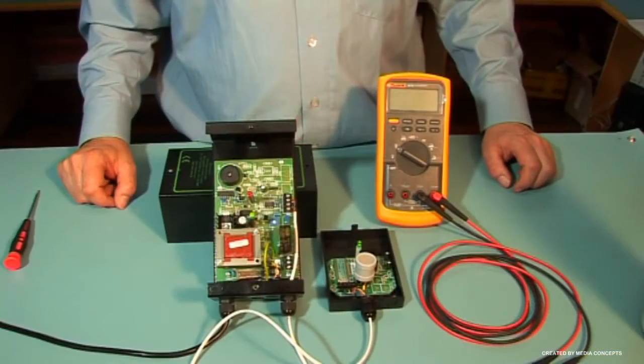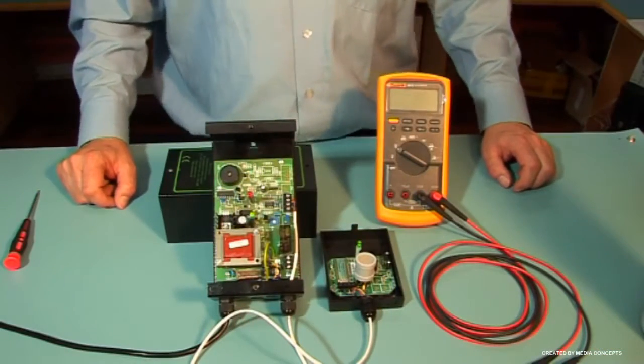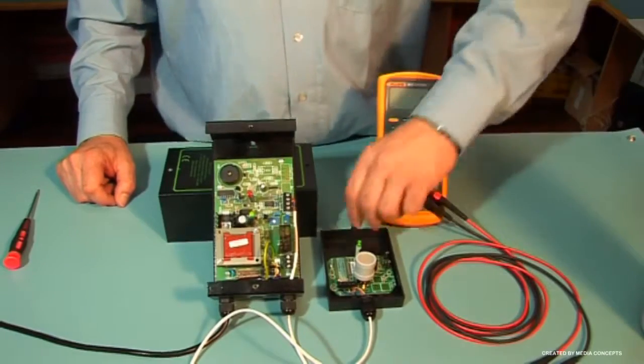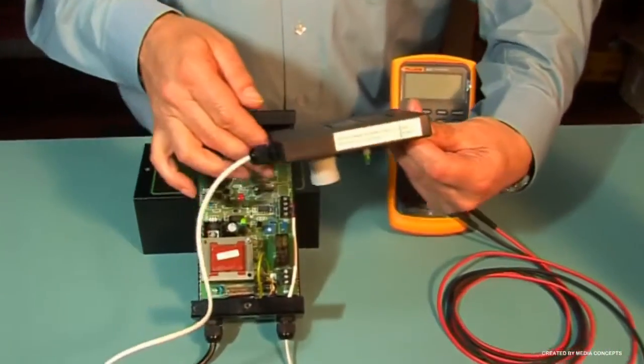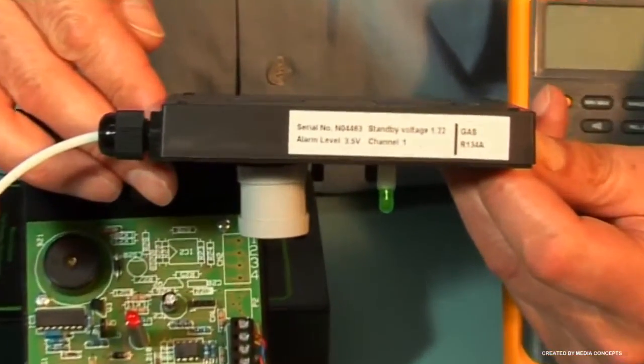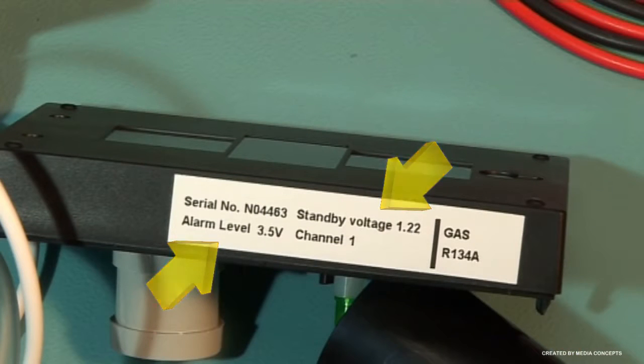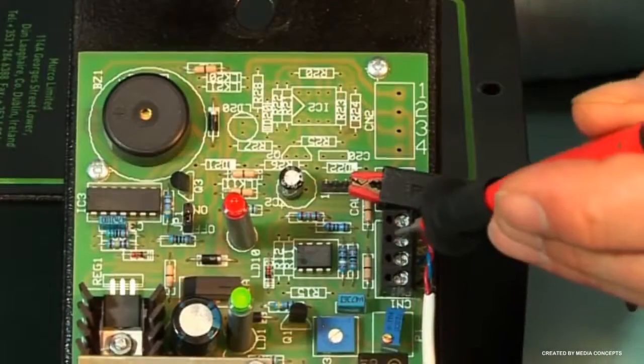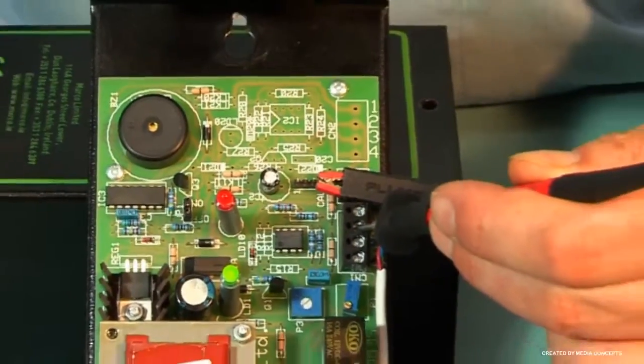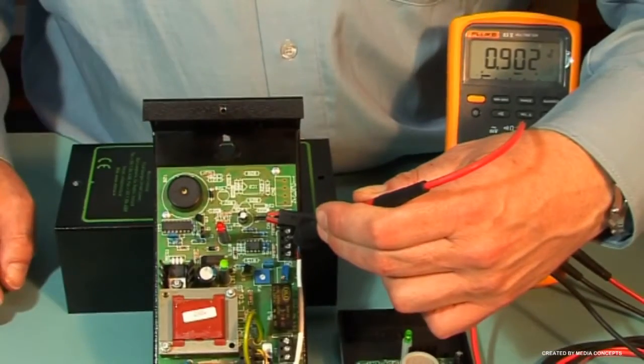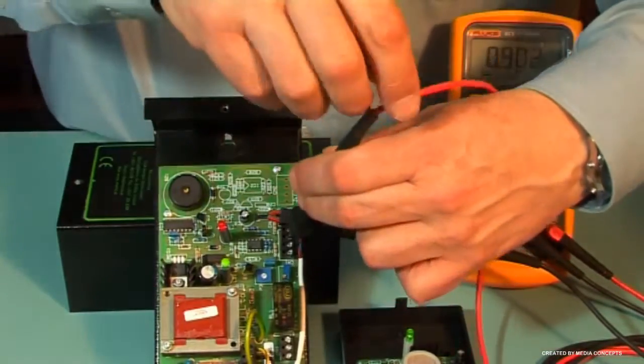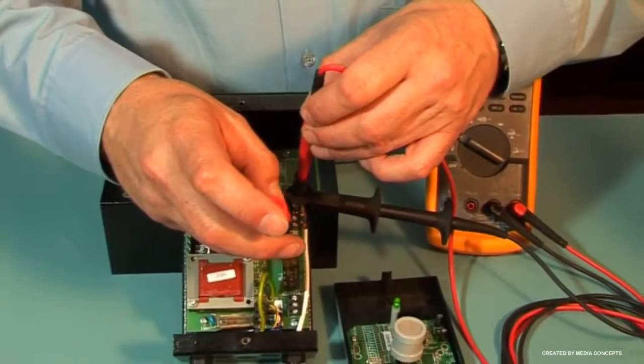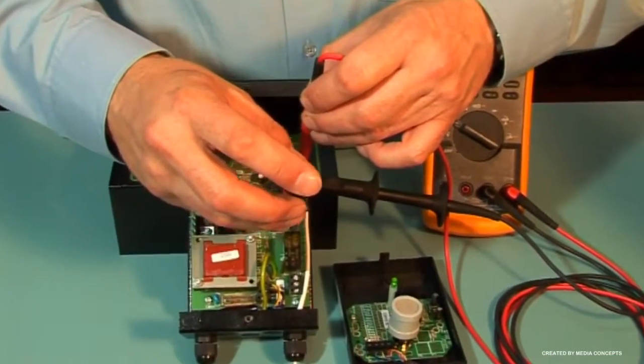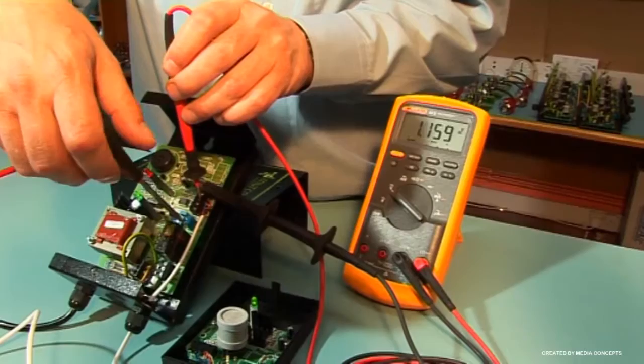The electrical setup of the 1-level system will be shown using channel 1 for demonstration purposes. The rating label on the side of the MGD sensor gives you the standby voltage and alarm voltage factory set points. These values were established during the initial factory calibration of the unit. So with your voltmeter between pin 4 on the CAL header and pin 2 on CN1, check and record the voltage. If different to the label factory voltage, then adjust P1 to the standby voltage as per the rating label.